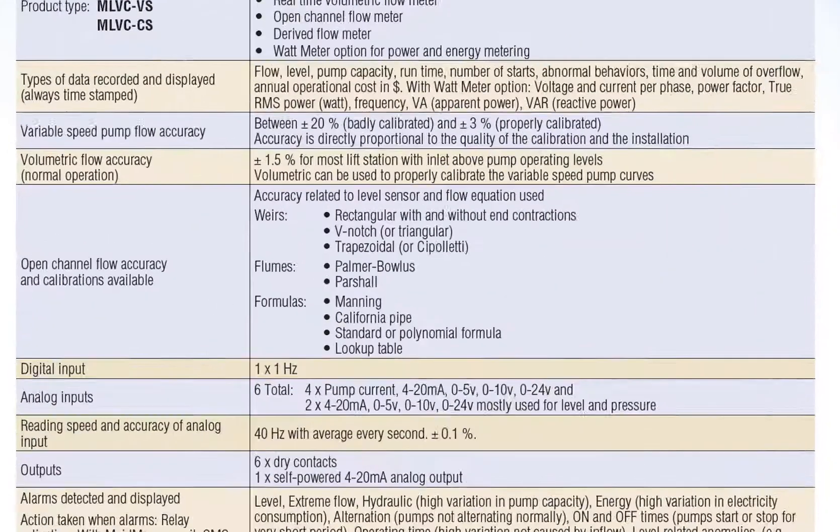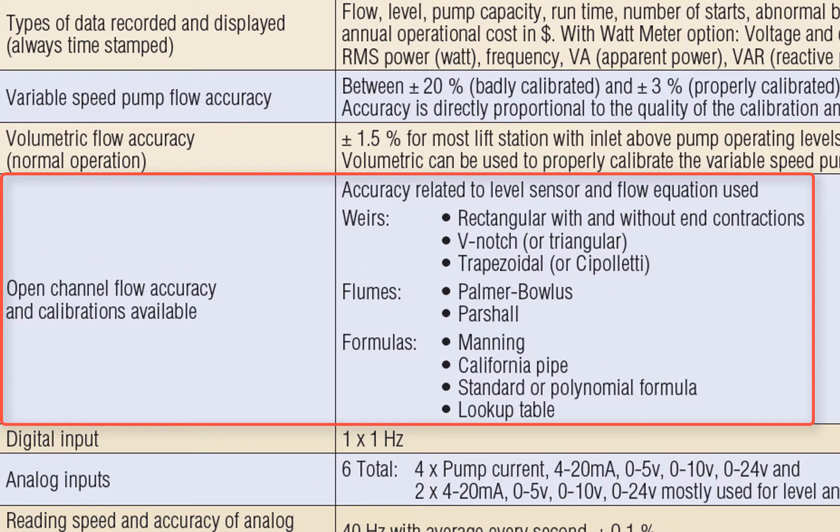One feature I haven't mentioned: if you have an outflow pipe coming out of your lift station so that water is diverted somewhere else during high levels, you can specify an open channel flow meter to calculate the volume of water diverted to another site, because the Volucalc Hybrid is also an open channel flow meter. You can select what type of weir or flume or formula you want to use, and it will calculate based on that. Of course, you need an analog level sensor.